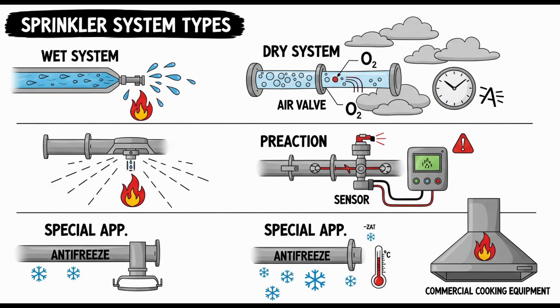That's a vital protection. A check valve is also typically required between the QOD and the intermediate chamber of the dry pipe valve if the QOD needs protection against submergence after system operation. Submergence. Yeah, after the main valve trips and water fills the system, this check valve prevents that water from flowing back into the QOD, potentially damaging it. If the QOD's design actually requires pressure feedback from the intermediate chamber, then an indicating valve that can be locked or sealed open is allowed instead of a check valve. Lots of specific plumbing details to ensure it works only when intended and doesn't get damaged.